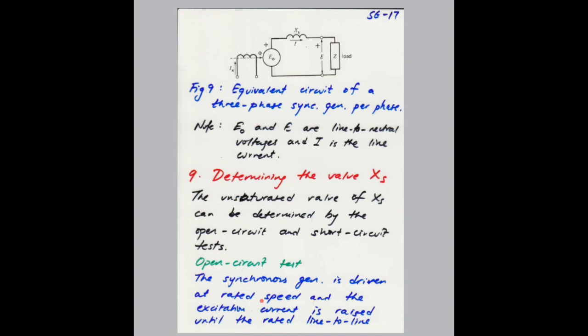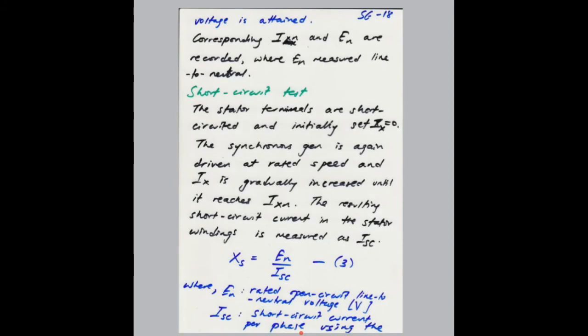Right, so in the first section, we will look at the open circuit test. Here we drive the generator at rated speed, right? And we slowly raise the current Ix from 0 until we can measure the rated line-to-line voltage across the terminals, and the corresponding excitation current. The nominal voltage is recorded, where En is the line to neutral voltage. So if you're measuring it line to line, you'll have to convert by dividing by √3. But if you're measuring line to neutral, then you don't need to convert.